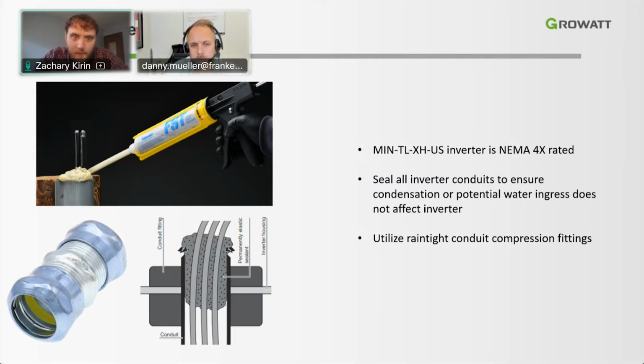But from some of my experience out in the field, and just in the industry, I do recommend utilizing a type of sealant to plug those conduit holes. I would also recommend utilizing rain-tight conduit compression fittings. These are fittings that have the ability to seal the end of the conduit. I recommend this as well. It's important to mitigate the amount of water ingress that may be happening if these were not used.